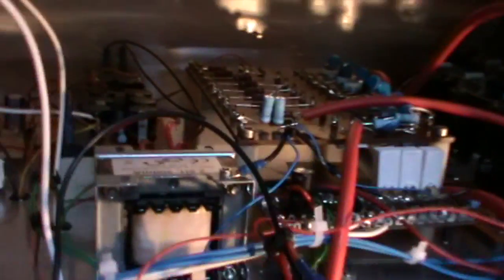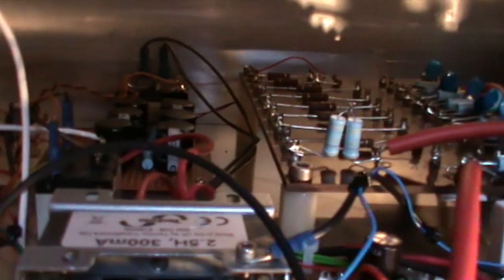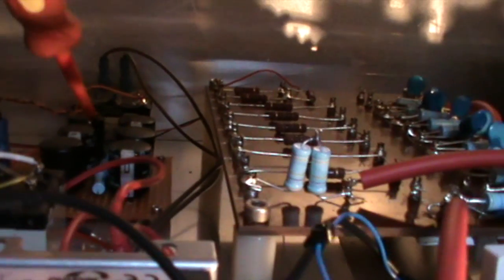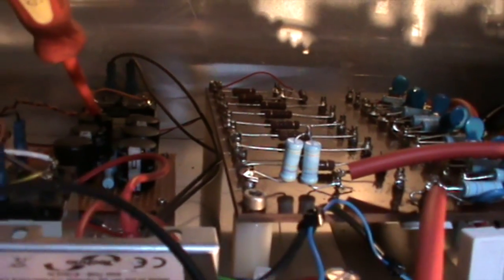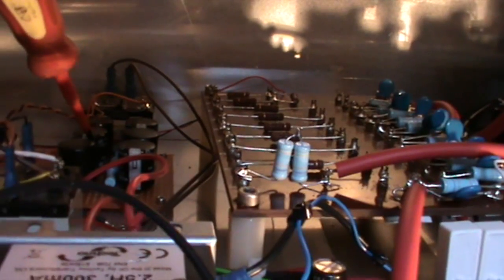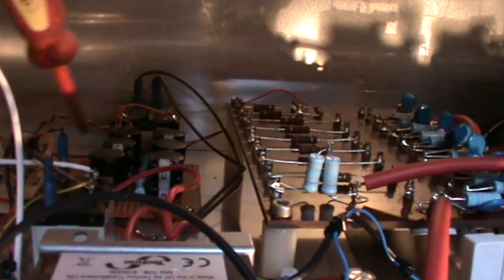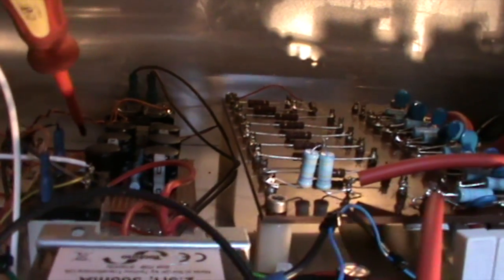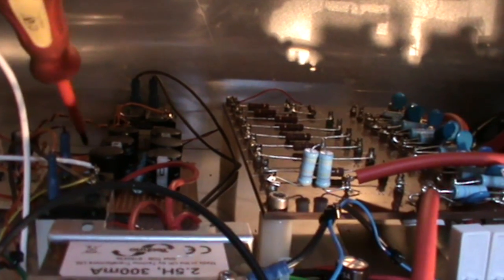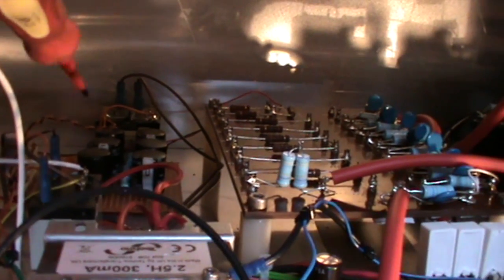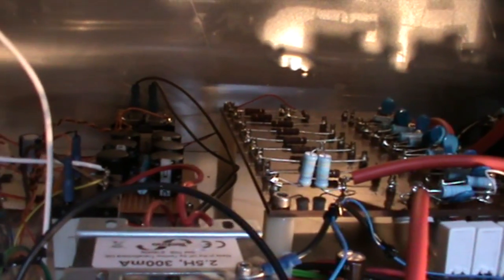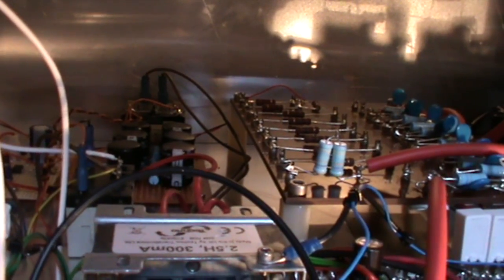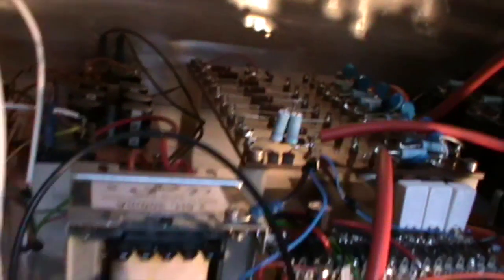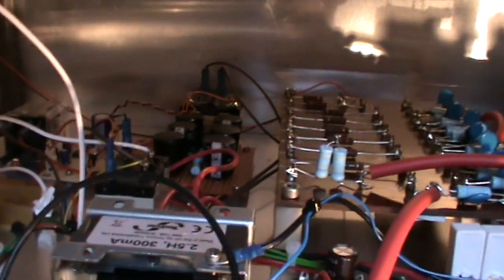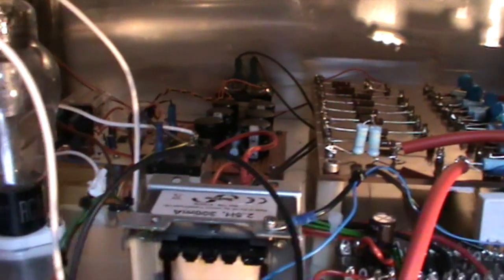At the very back here, we've got some boards for rectification and smoothing capacitors for the screen. There's a number of relays here, part of the soft start system for the HT. Obviously when running this type of voltage, switching on gives a massive inrush current, so you need some sort of soft start mechanism, which is often required for high voltage power supplies.